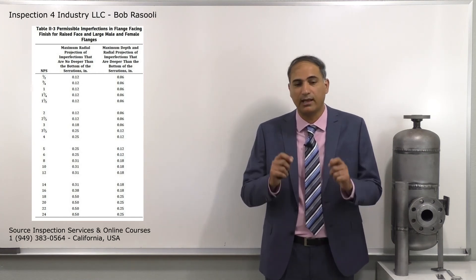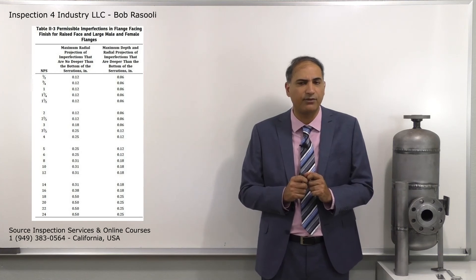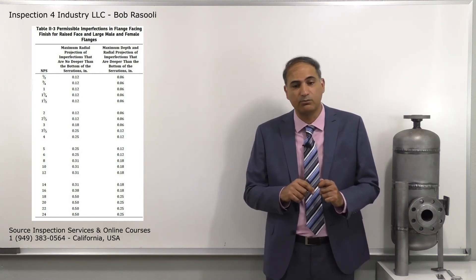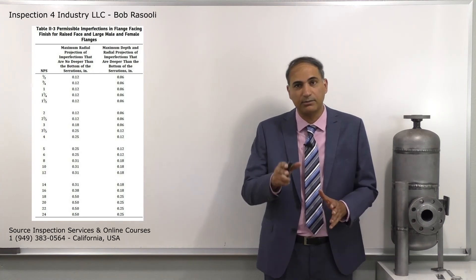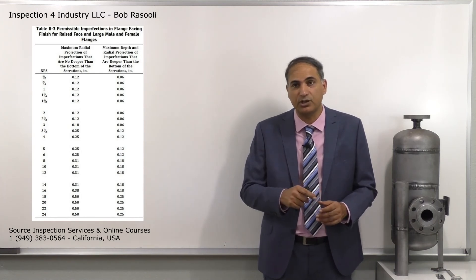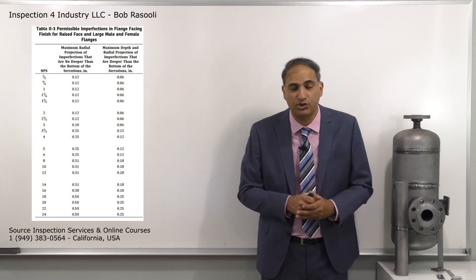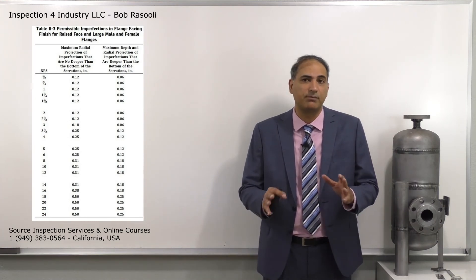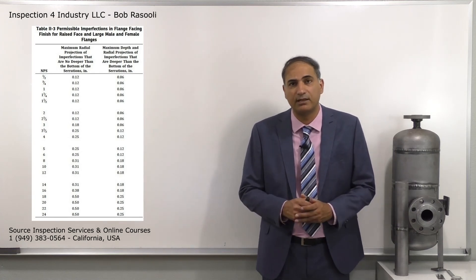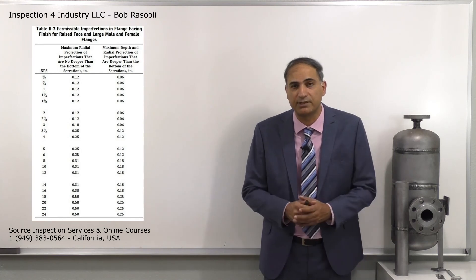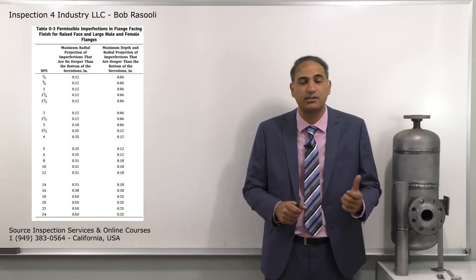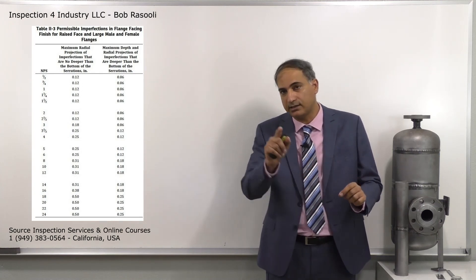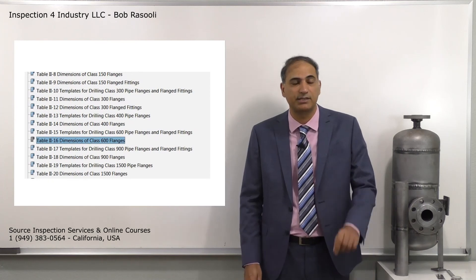To summarize the evaluation: first determine if the imperfection depth is less than half the serration depth - if so, ignore it. If it's more than half but not deeper than the serration, use the middle column. If deeper than the serration, use the last column with more stringent requirements. For the exam, close-book knowledge includes the half-depth rule. For table-based questions, locate Table 2-3 using your bookmark, input the flange size and damage size, and select the correct answer.